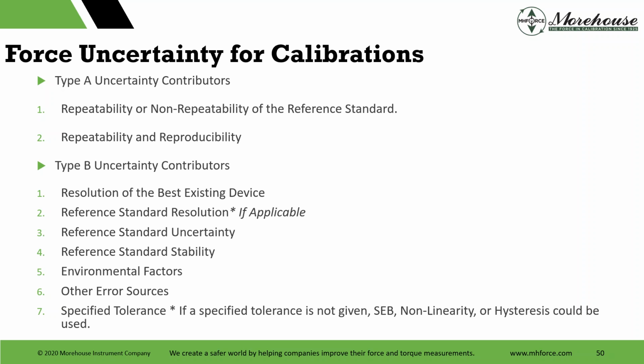And if we're looking at force, typical force uncertainty for calibrations, these would be, you have equipment and you want to do calibrations for somebody else. This is what we typically would see. Type A: repeatability, non-repeatability of the reference standard, repeatability and reproducibility. These are usually done in your equipment with your machines. Then you have Type B: resolution of the best existing device. We've made mention of that earlier. That's the device you really want, something awesome, maybe a second load cell, maybe a really good stable system. You can use it for statistical process control. You can use it for checks. Use it for ILCs. You can use it if it's calibrated by dead weight. You could use it to meet some proficiency testing requirements with ILCs.